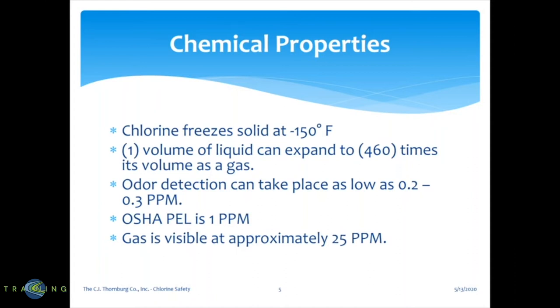Odor detection can take place as low as 0.2 to 0.3 ppm parts per million, meaning it doesn't take very much of it for you to smell it in your process. The OSHA permissible limit is one part per million, which is relatively low. Gas is visible at approximately 25 parts per million — you can see the yellowish green gas hovering in the air.